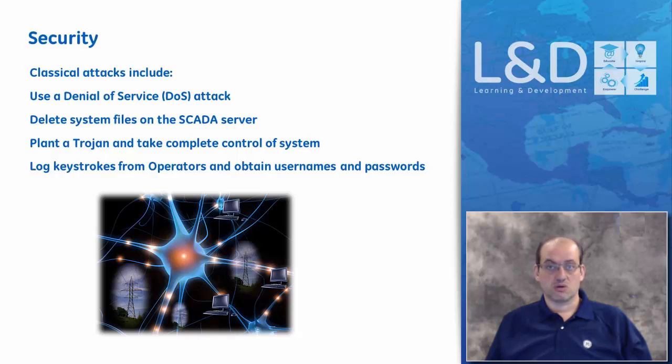That information might be required for a regulation, so there are legal implications. When you're managing a SCADA system, all of these protocols have to be made clear, that a USB stick cannot be used. Sometimes it has to be clarified not only as a policy on your machine, but also as a policy in your substation to all the workers. Even if the operating system prevents a person from using a USB, it has to be clear to everybody that nobody can use a USB memory stick, because that might cause bigger damage to the machines in your substation.